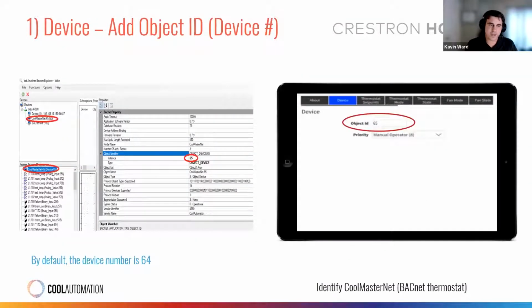Starting with step 1, adding the device. On Yabe, you can see the CoolMasterNet. In this example, it's object or device ID 65. Underneath the devices in the bottom left-hand side of the picture, you can see each of your object points. These will appear as a generic description at first. As you click on them, they'll begin to translate, the object will be defined so that you'll actually see each of your objects clearly with a clear description. So from your Crestron Home, the device tab, enter the object ID. If there's multiple devices, 64, 65, or however you have it configured. In this case, we see 65, so we enter 65. We typically leave the priority as a manual operator 8.